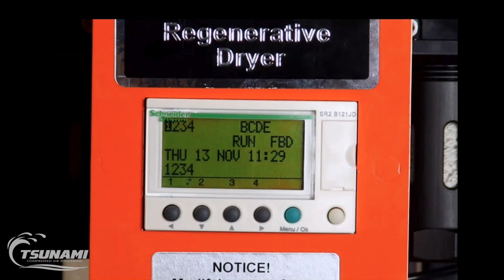So right now this dryer has retracted both of its pistons, and it assumes there is no airflow going through this dryer. This dryer is not regenerating, it's not sweeping air, which means we are not wasting or using any air to regenerate those towers. Now let's just say that signal is coming from a compressor. So the compressor has hit an unload mode, and when it has unloaded, it sends a signal. We use a dry contact that closed, and it's now allowing us to complete the 12-volt loop. And this PLC is receiving a 12-volt signal that says the compressor is in an unloaded state. It is not manufacturing air. So we don't need to keep having the dryer cycle back and forth.